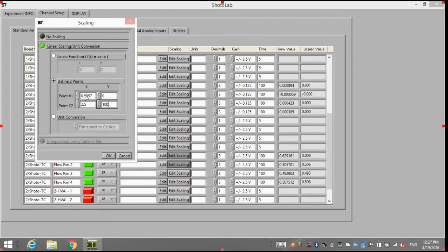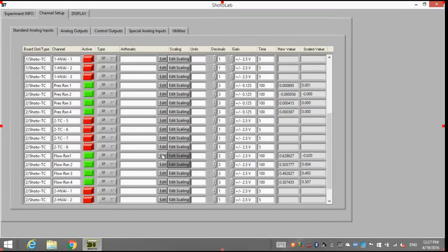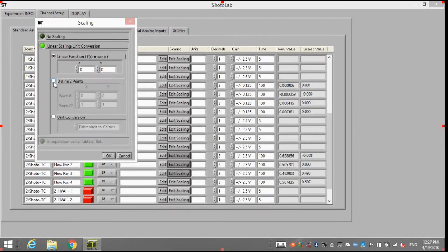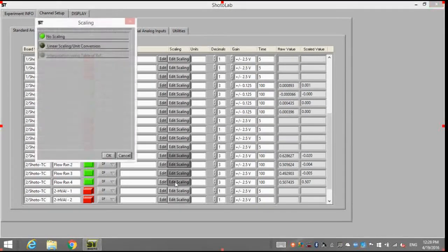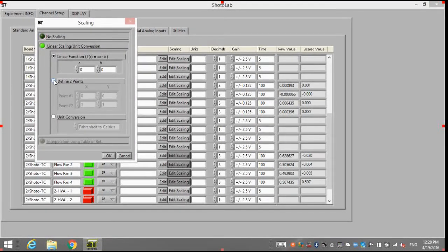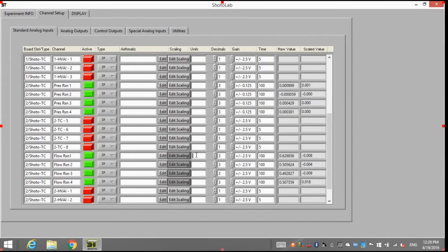Click on the third flow meter. You see that that's reading 0.493 at 0. Let's enter that. And click OK. And finally, the last one, the fourth channel, is reading 0.507 at 0 flow. And as the other ones, 2.5 volts at a full value reading of 100 cc's per minute. Let's type in the units for all of these: cc's per minute.